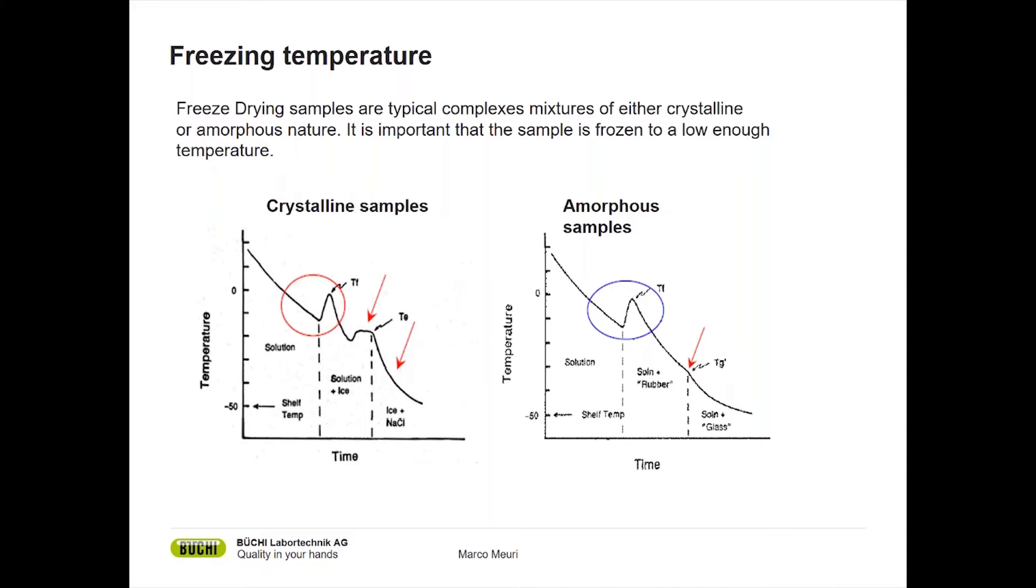Often household freezers are used for freezing samples. They only go to about minus 18 to minus 24 degrees, and this is usually not enough to really freeze your samples. So one hint from me: if you use a freezer, please use at least a minus 40 degrees freezer to freeze your freeze drying sample.